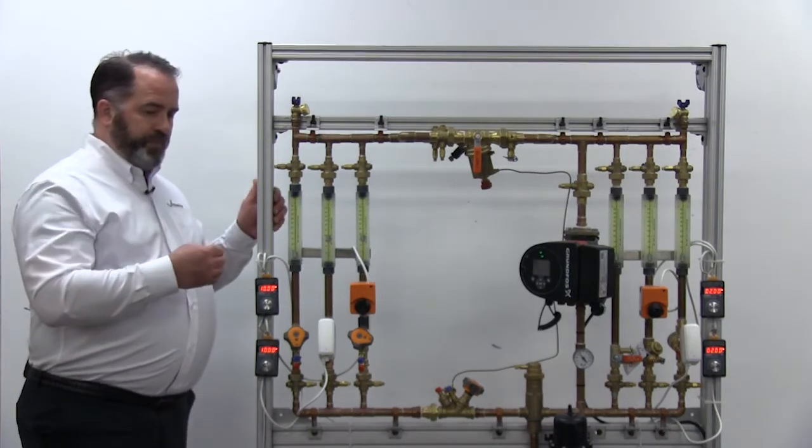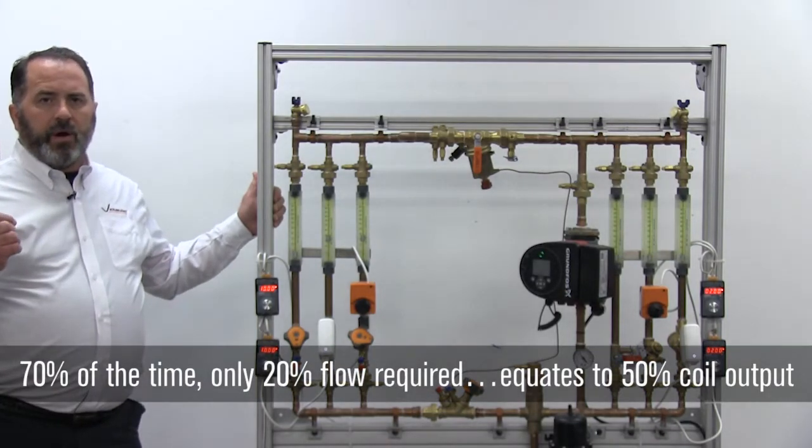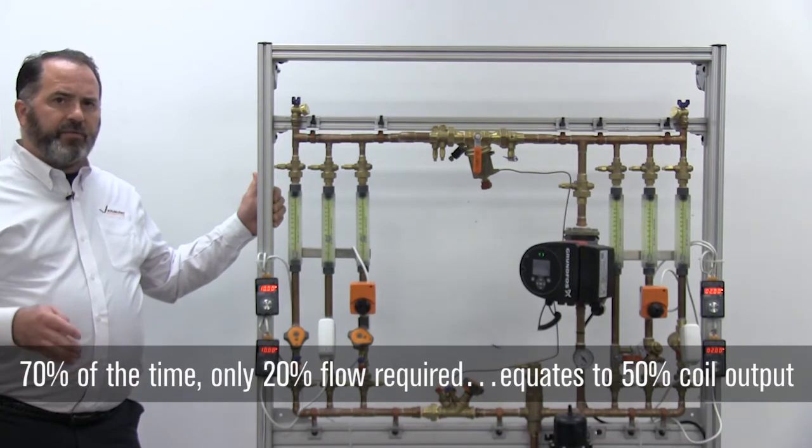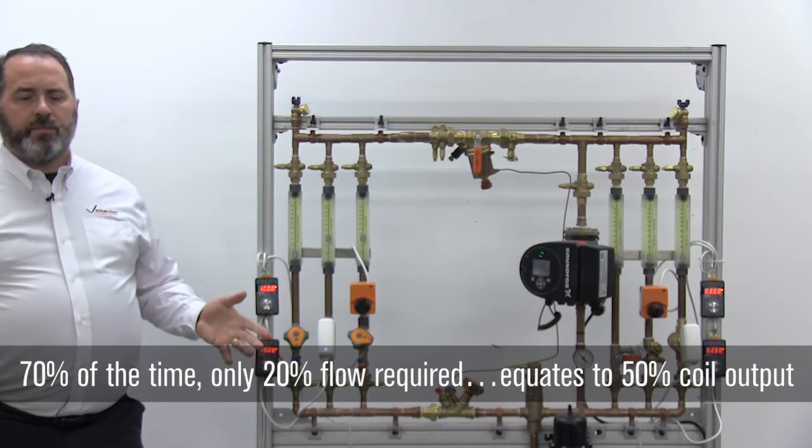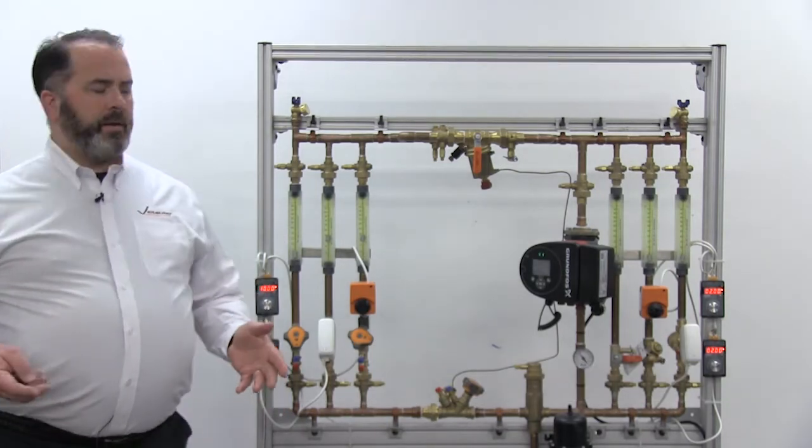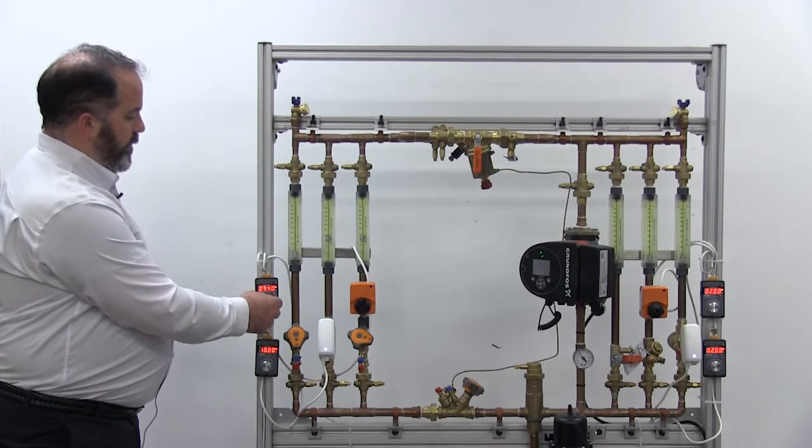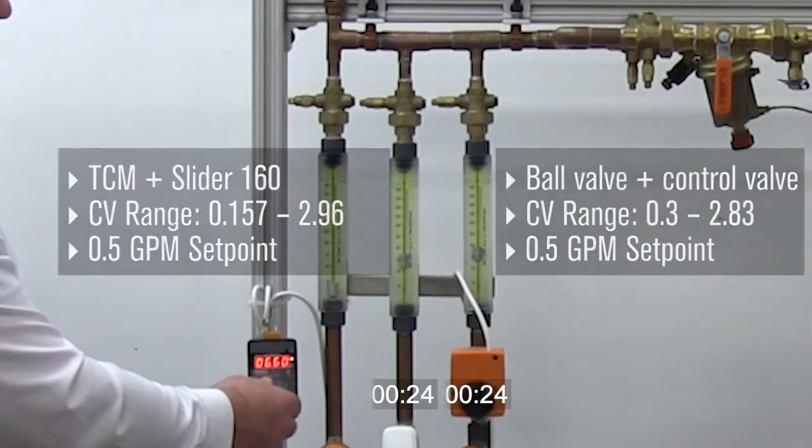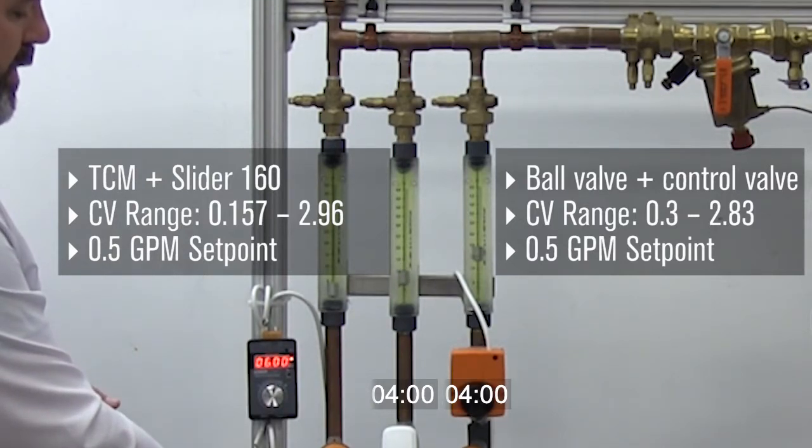Let's go back to our 70% of the time you're only requiring 20% of the flow through the valve, because 20% of the flow through the valve translates to 50% of your coil output, which is where most systems typically operate. So in order to do that, it's a characterized control valve, so we want to take it to 50% of the signal. In this case it's 2 through 10 volts, so it's 6 volts. Take both of those to 6 volts and we'll allow them to operate.